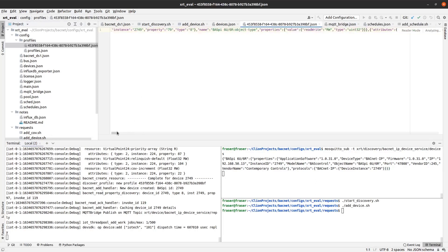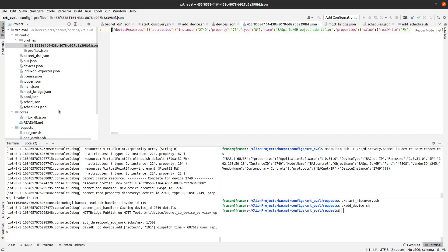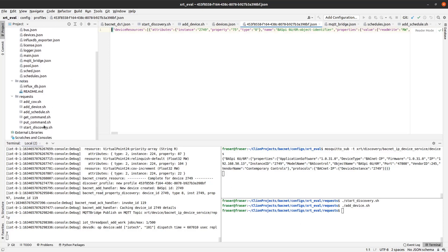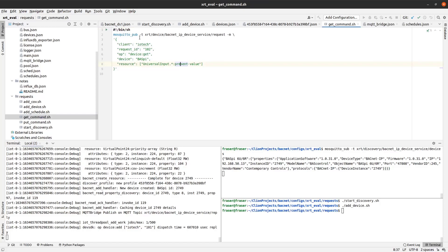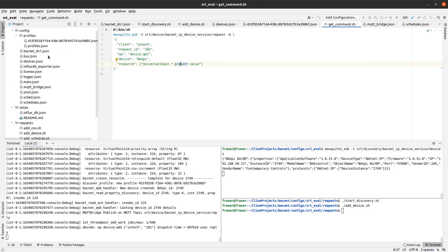This file contains the information on all the resources or data points and their addressing that can be read or written to by the XRT BACnet device service. The next thing that I will show is how to issue explicit MQTT requests to read and write data from and to the BACnet device. You can see the JSON payload for the request to read the values for all of the universal inputs. Notice the use of the wildcard to enable multi-reads.